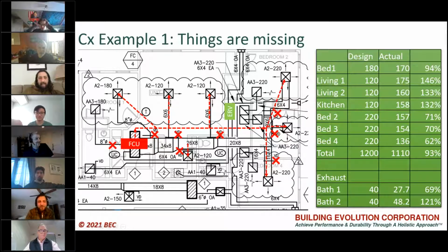One of the morals is if you're going to rely on volume dampers, whatever you call them, if you're relying on manual dampers or some sort of control, there needs to be access provided. That's one of the things that a commissioning agent could see in the design phase. You look at the reflected ceiling plan. Does it indicate that there are access panels in the ceiling? If not, it's probably not happening. Even if the dampers are there, nobody's going to use them. Yeah. Unless they're really small.